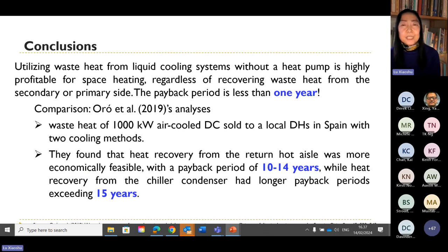Utilizing waste heat from liquid cooling system without heat pump is highly profitable for space heating, regardless of recovering waste heat from primary or secondary site. And our solution shows that the payback time is less than 1 year. And our result outcome, the state of art existing, for example, the existing literature published in 2019 for 1,000 kilowatts air cool data center analysis with two cooling methods. Their payback periods are 10 to 14 years and 15 years respectively, significantly or much longer than our result.